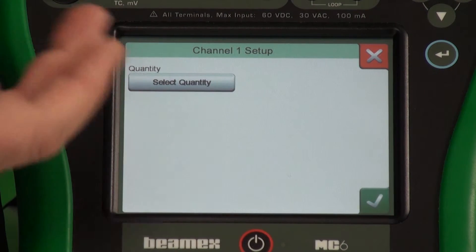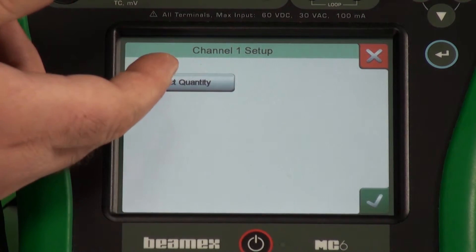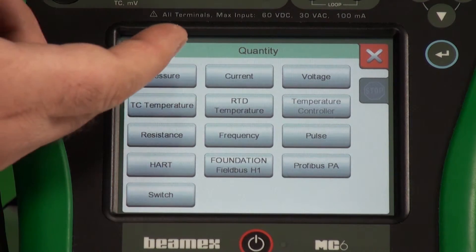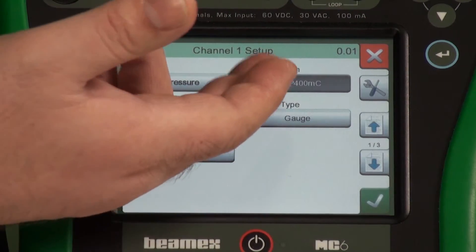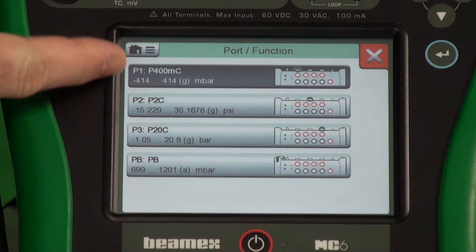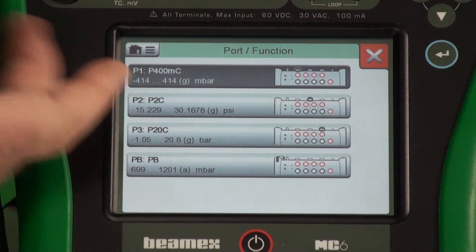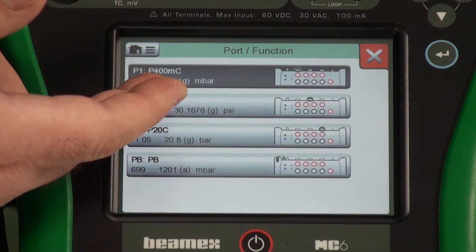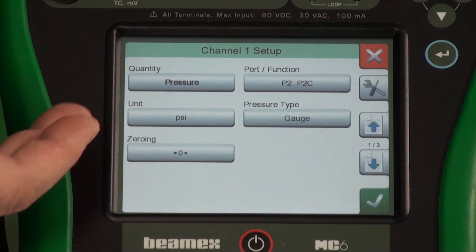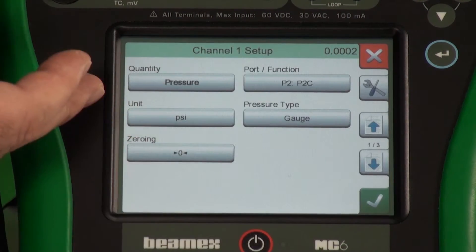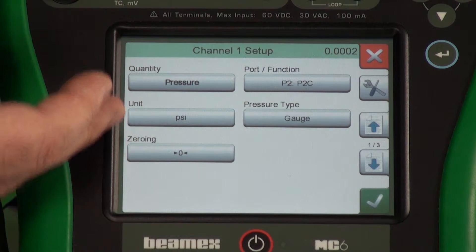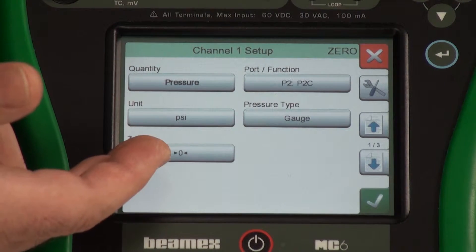We'll start by defining channel number one. In this case, I'll pick a quantity and I want pressure. We're going to measure the pressure coming out of this pump. I'll pick my pressure port. I have my options here — I'll take my middle one. This is up to 30 psi. Pressure type: gauge. I could pick absolute, but gauge is what I want here. And I have the option to zero my module as well.